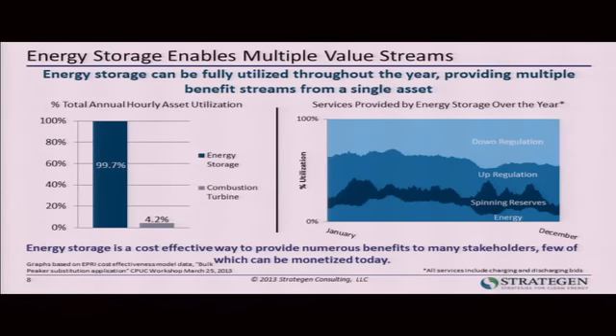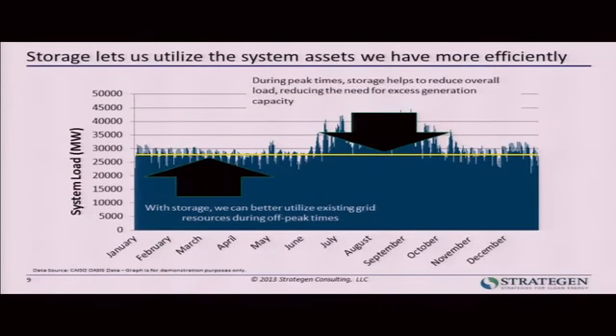So when you think about that, you've got more range, a faster response, and more benefits. Storage is the better way to do things. It's not how we've been doing things, but it's the better way to do certain services that are needed on the grid today. If we had some storage throughout our electric power system, we could take that previously poorly utilized system and flatten our load curve. The goal is to utilize the existing assets we have much more efficiently, taking that average load factor up from 50% to 75 or 80%. That's low-hanging fruit.